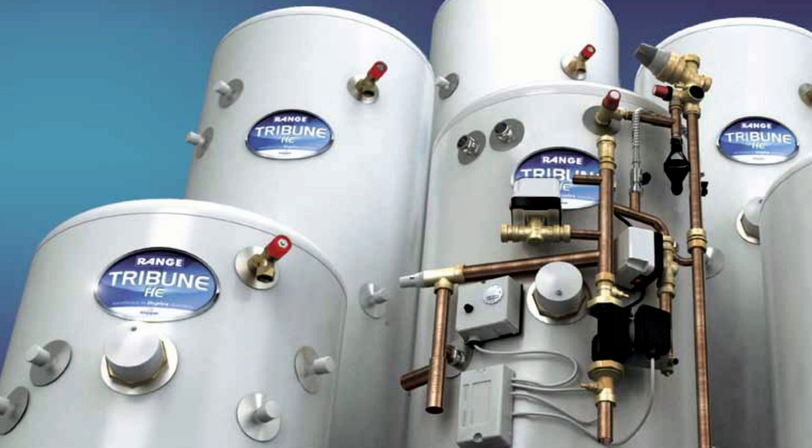So the rest of the system is pretty much exactly the same as a standard Y plan, and all we're really changing is the connection to the cylinder thermostat. So rather than it just going via the thermostat and returning to the wiring centre, it goes to the thermostat, into the high limit thermostat, usually in the same container, and then the output of that goes to the two port valve, and then the switched output from the valve is what returns to the wiring centre.